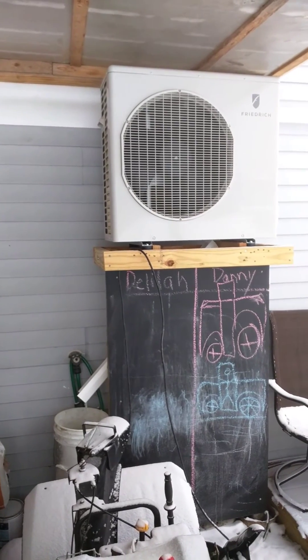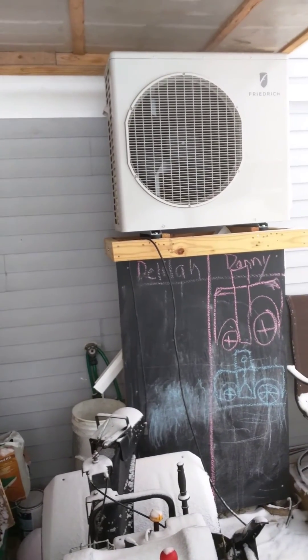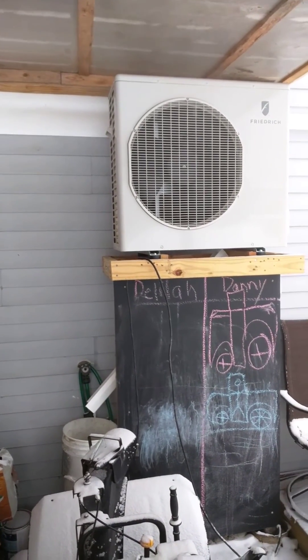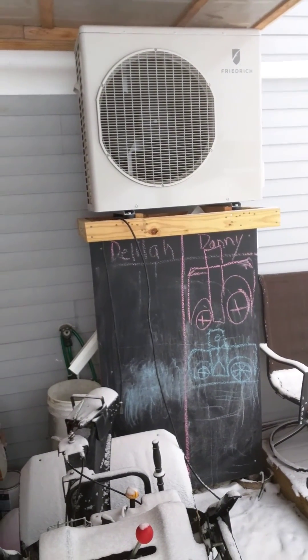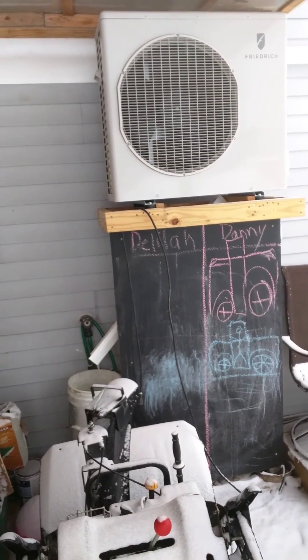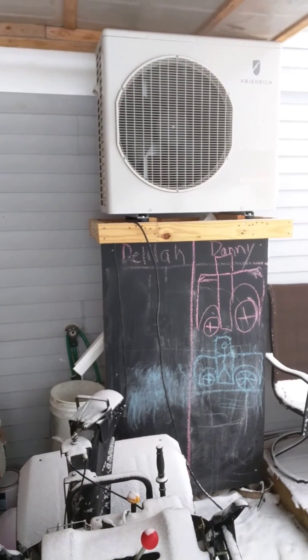The other units are Fujitsu 12 RLS 3H. This is a Friedrich — a rebranded LG HLV unit, which is an extended pipe unit. It's a 24,000 BTU. It's the same outdoor unit for 24, 30, and 36,000 BTUs. So running this unit, you should get a longer life expectancy out of it because it's a unit that's utilized for up to 36,000 BTUs — not running at maximum capacity at 24,000. Very satisfied so far.